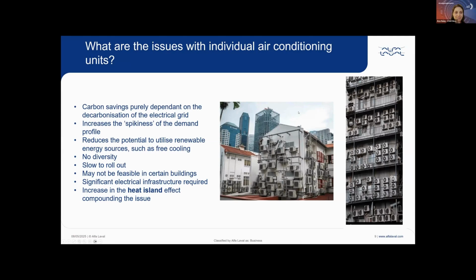Let's go again. Right. So when we look at the individual approach, we can see here some of the aesthetic issues that we'll come across, particularly if you look at individual apartment buildings. But there are many other negatives to this approach to cooling. You lose the diversity that comes with the district approach. So you have to be able to supply instant electricity as those peaks change, and you get a very spiky demand profile as people switch these units on. So you have reduced or zero diversity compared to the district approach. It's very slow to roll out. It's often not feasible in certain buildings, and it needs a significant increase in electrical infrastructure.